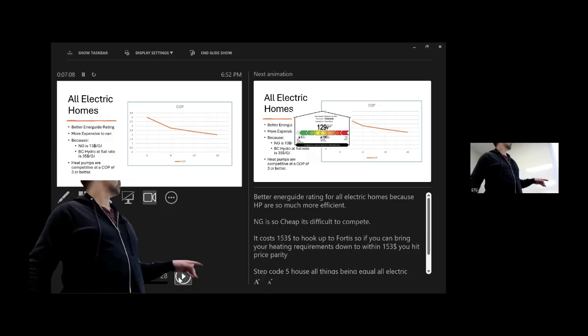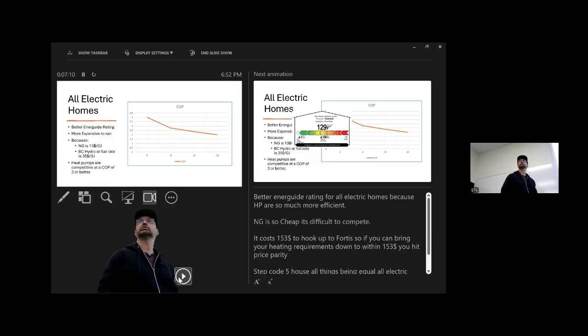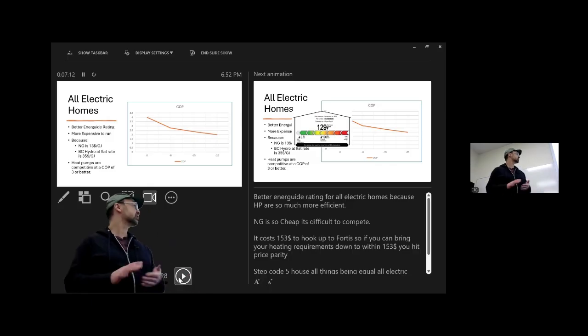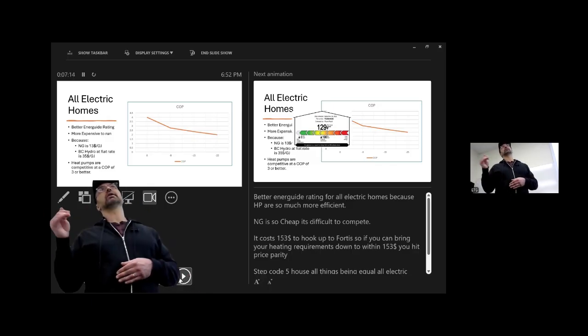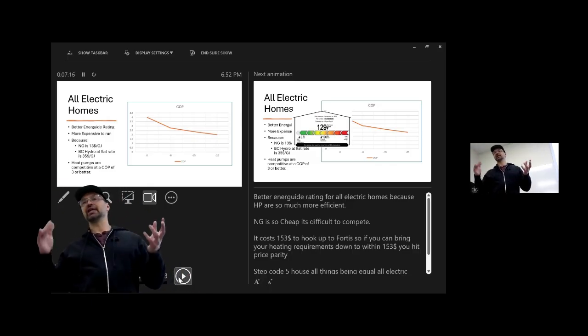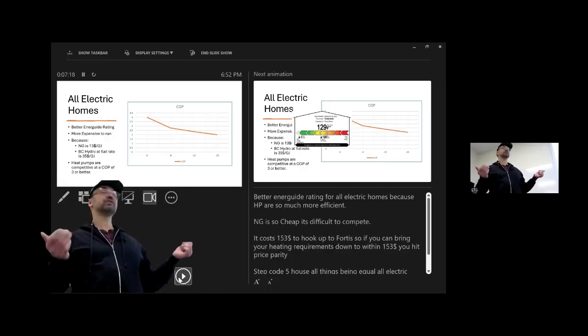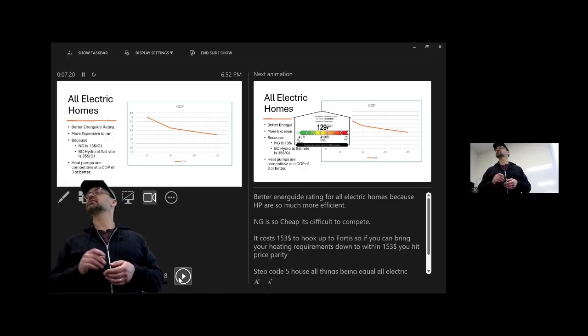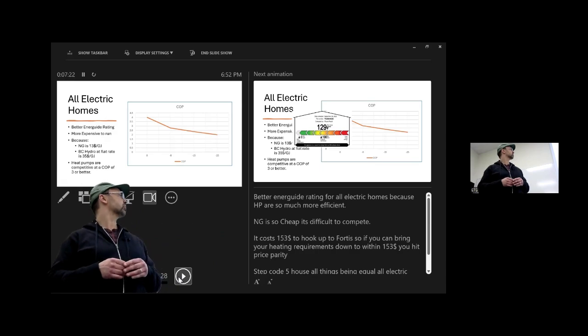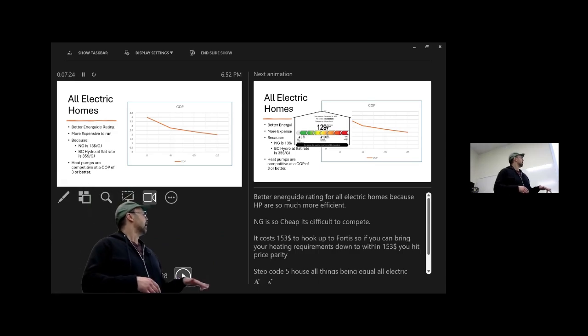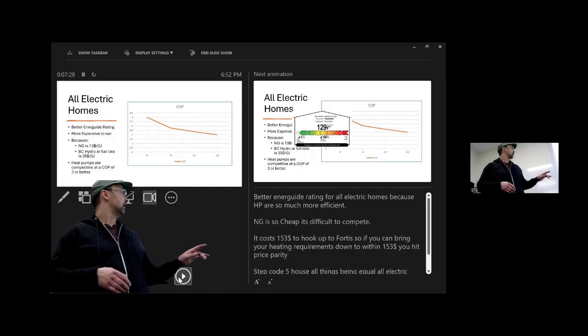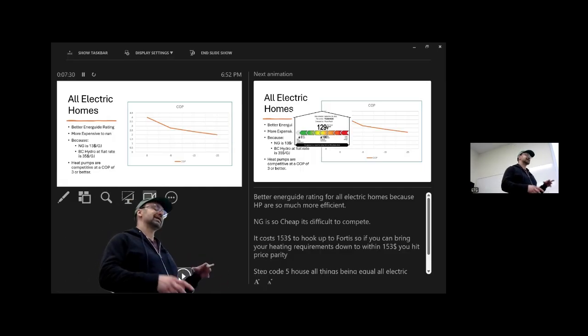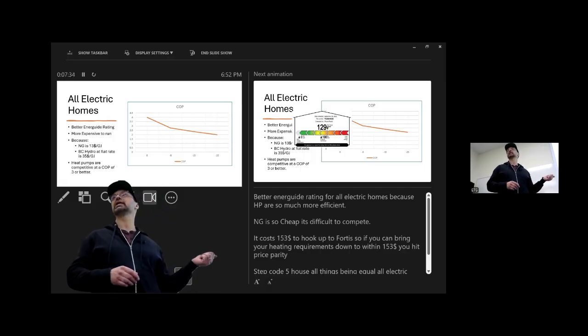However, it's more expensive to run because natural gas is so cheap. Natural gas is $13 a gigajoule. BC Hydro has got a bunch of different rates you can get. I took the flat rate, which is about 12.65 cents per kilowatt hour, which comes out to about $35 a gigajoule. So for a heat pump to beat natural gas on just a cost basis, it needs to have a COP of 3 or better.